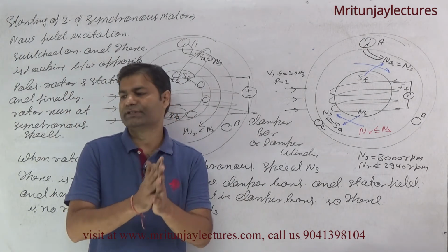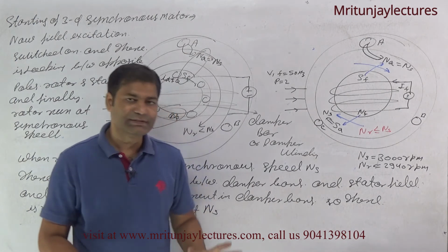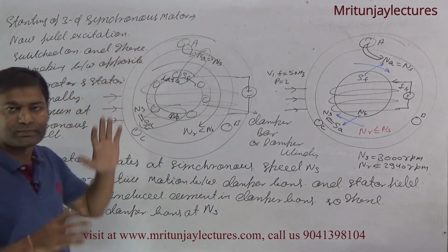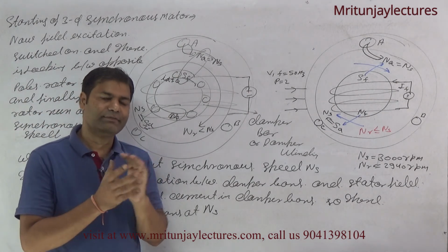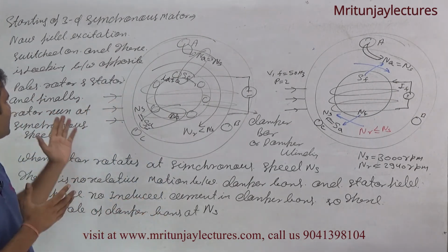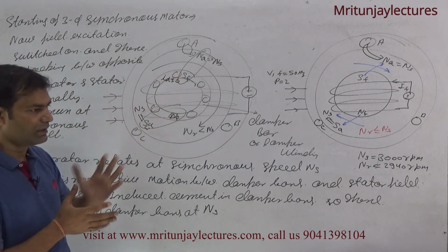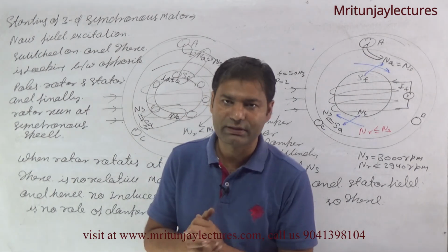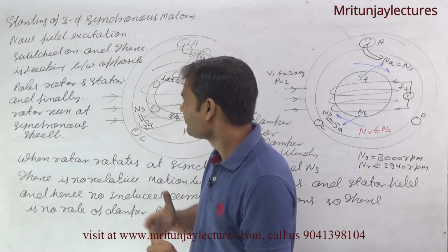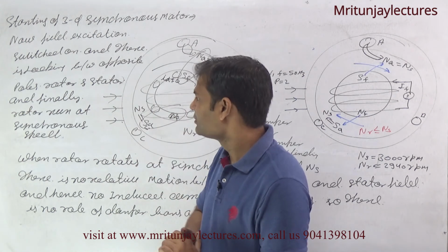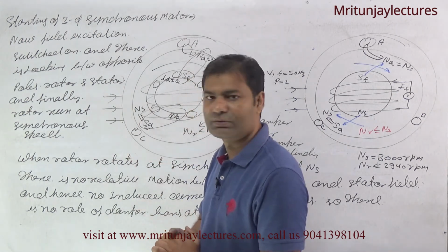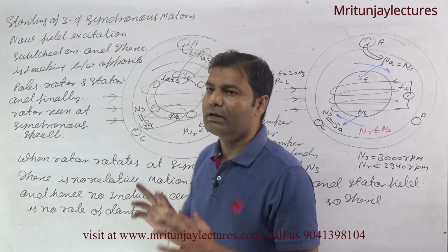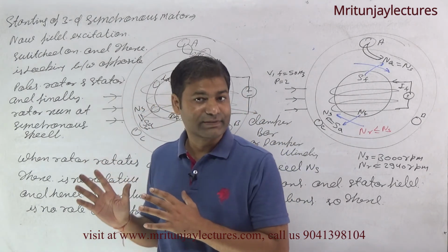Now how to start a three-phase synchronous motor? With the help of the damper bar; the main role is the damper bar. Sometimes a question asks which type of damper bar, basically that is a squirrel cage rotor. I have already discussed in the induction machine what the damper bar is. The damper bar is provided on the rotor. Now it starts as a three-phase induction motor.